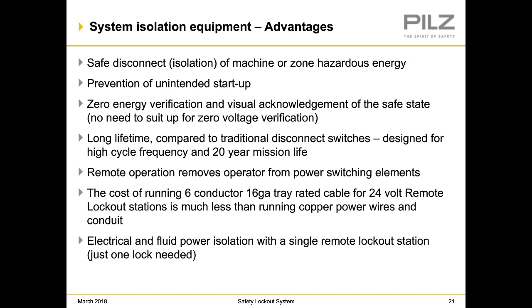A long lifetime compared to traditional disconnect switches. They're designed for a high cycle frequency and a 20-year mission life. Remote operation removes the operator from the power switching elements. They're only standing in front of a little small disconnect that only has 24 volts in it. Also, you've got to consider the cost of running six-conductor, 16-gauge tray-rated cable for 24 volts is much less expensive for these remote lockout stations than placing a disconnect switch at a convenient access point where you would have to run copper power wires and conduit.